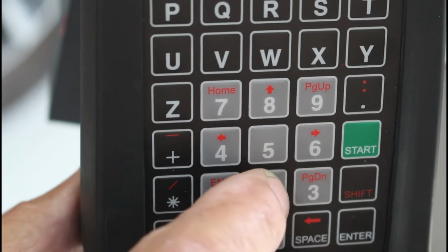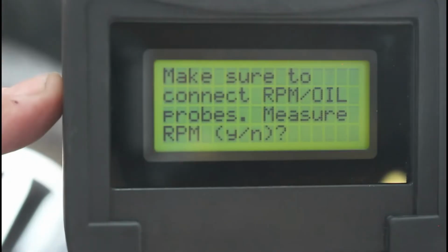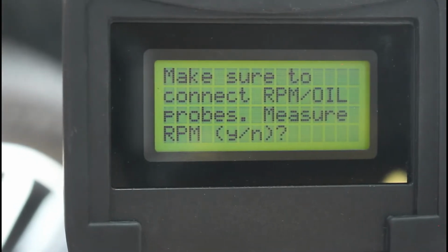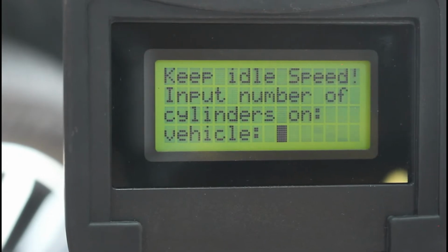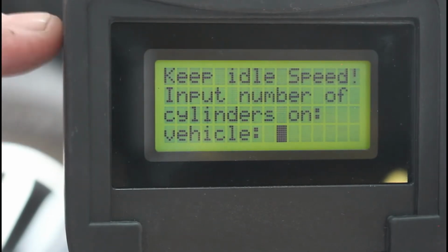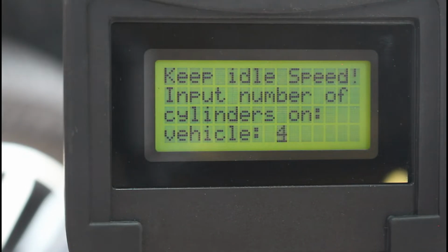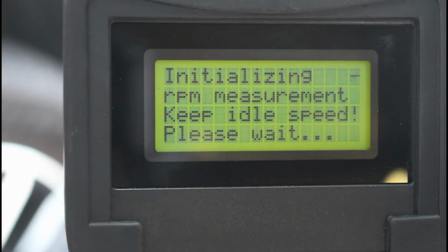As we go down, we can go to set up. You'll see it flashing on the setup cylinders. We hit our enter button down here. It says make sure that we connect the RPM and oil probes. Have we done that? Yes, we have. We press Y on here and then enter. It says keep the idle speed, input number of cylinders. We've already done that. We've said 4. We hit enter there again.